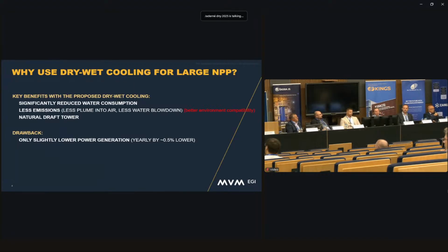What are the key benefits with dry wet cooling? Why should we use dry wet cooling for large nuclear power stations? One is the substantial water consumption reduction. The other one is an environment protection related issue. There are less emissions from the cooling tower. Emissions at the top of the cooling tower, or emissions, for example, in the blowdown water from the cooling system.